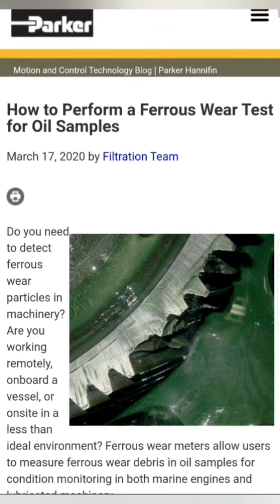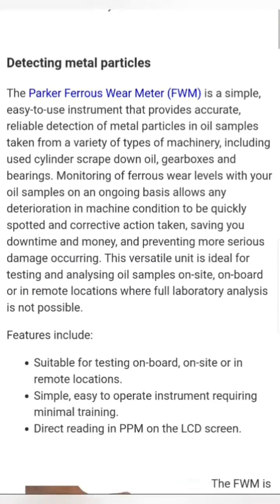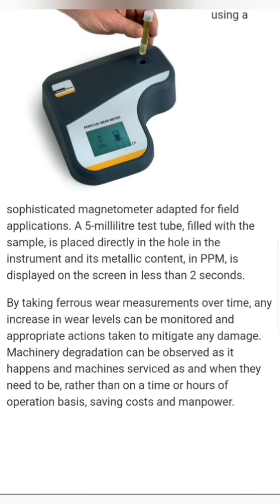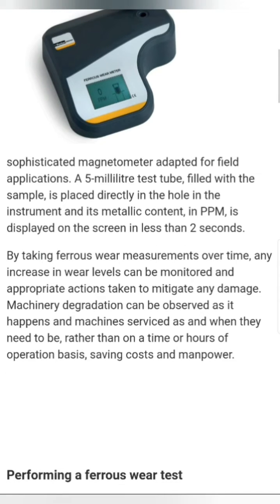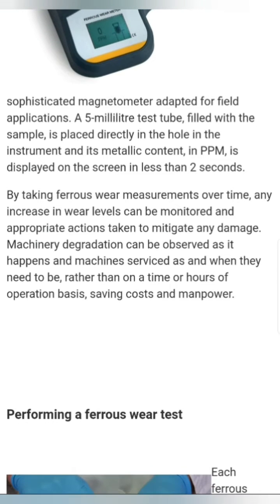This is the website for the Parker Kittiwake. We will move directly towards performing the ferrous wear test. The meter is constructed using a sophisticated magnetometer adapted for field applications. A 5 millilitre test tube filled with the sample is placed directly in the hole in the instrument and its metallic content in ppm is displayed on the screen in less than 2 seconds. By taking ferrous wear measurements over time, increments in wear levels can be monitored and appropriate actions taken to mitigate any damage.